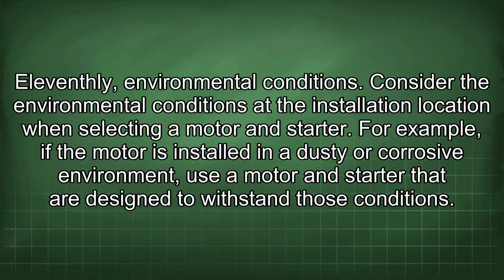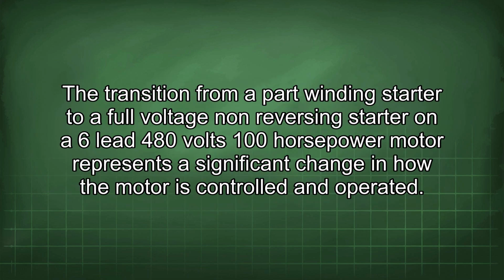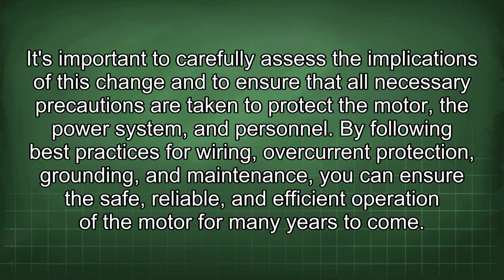11thly, environmental conditions. Consider the environmental conditions at the installation location when selecting a motor and starter. For example, if the motor is installed in a dusty or corrosive environment, use a motor and starter that are designed to withstand those conditions. The transition from a part-winding starter to a full-voltage non-reversing starter on a 6-lead 480 volts, 100 horsepower motor represents a significant change in how the motor is controlled and operated. It's important to carefully assess the implications of this change and to ensure that all necessary precautions are taken to protect the motor, the power system, and personnel.